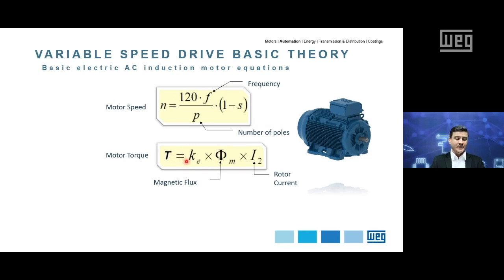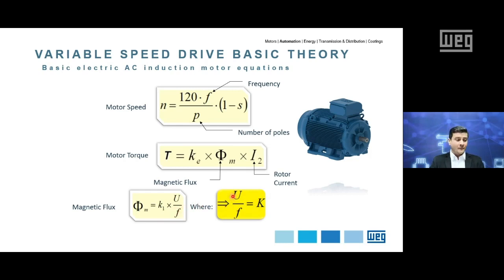Another important equation that we need to review is the motor torque. Motor torque is given by a constant multiplied by magnet flux multiplied by rotor current, which can be considered constant as well. We know that some applications require constant torque, and that's why it's important to give special attention to the magnet flux equation. Magnet flux is given by a constant multiplied by voltage divided by frequency. In this case, the variable speed drive will keep this relation constant, then the magnet flux will be kept constant, and therefore the motor torque will be kept constant as well within rated conditions. Okay?